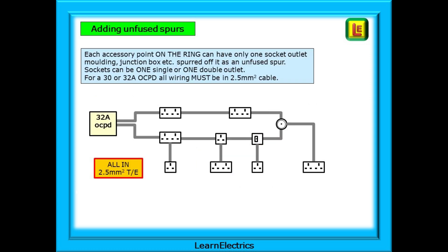When adding unfused spurs, we must follow the rules for safe functioning of the circuit. Each accessory point on the ring can have only one socket outlet molding, junction box, etc. spurred off it as an unfused spur. Sockets can be one single or one double outlet. For a 30 amp or 32 amp OCPD, all wiring must be in 2.5mm cable as shown here in grey.